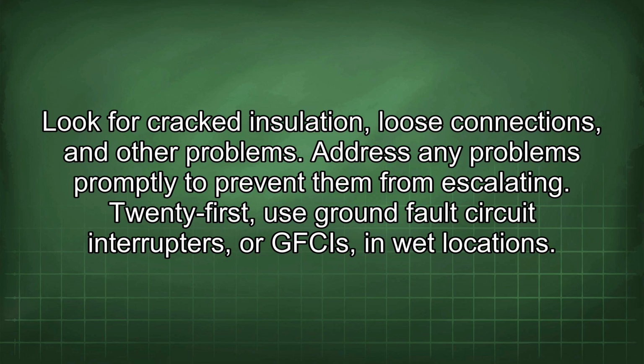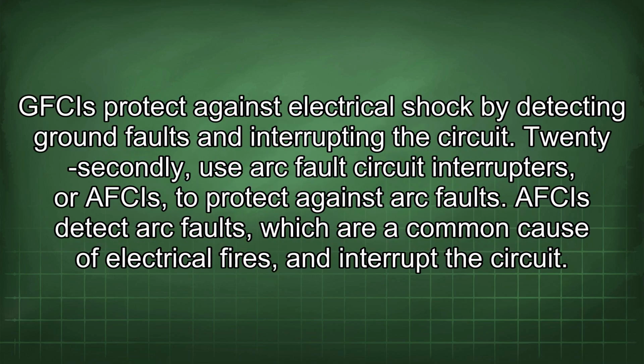21st, use ground fault circuit interrupters, or GFCIs, in wet locations. GFCIs protect against electrical shock by detecting ground faults and interrupting the circuit. 22nd, use arc fault circuit interrupters, or AFCIs, to protect against arc faults. AFCIs detect arc faults, which are a common cause of electrical fires, and interrupt the circuit.